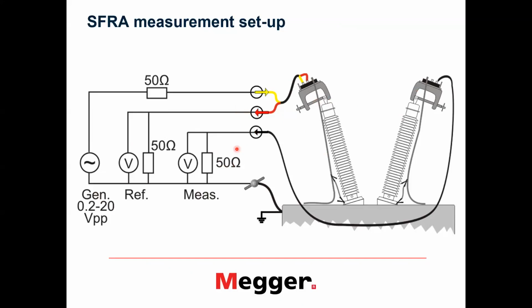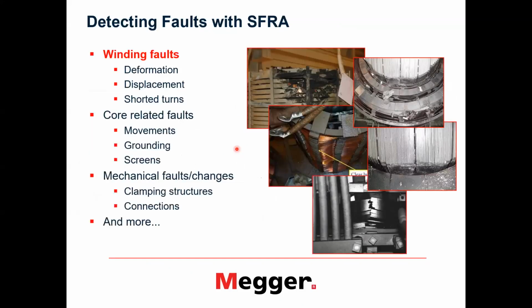So the setup is very easy, but using this simple setup we can detect different issues in the winding, such as deformations, displacements, shorted turns. We can detect issues with core-related faults like core movement, missing groundings, presence of screens or missing screens, as well as if the transformer itself has been subjected to some, I don't know, mechanical impacts so that it has moved inside. So the clamping structures and connections have been moved around and so on.